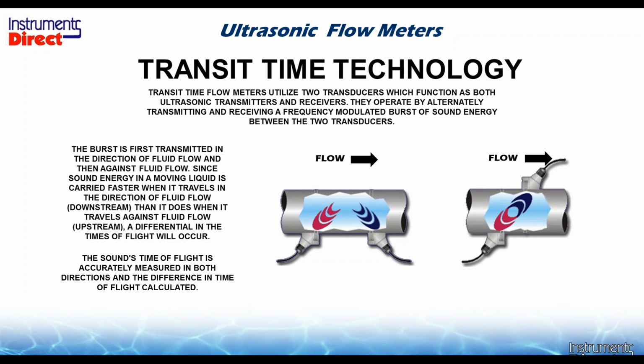Using a transit time flow meter, we have 2 cutaway windows here. Here's a traditional configuration, and this is a configuration which would look just like the man in the rowboat. Basically, we're sending a sound pulse across the pipe to the other sensor on the other side of the pipe. Flow's going from left to right. Then we send another pulse back to the original sensor, but because the flow is going from left to right, it takes a longer period of time to send the signal back, just like the man in the rowboat.